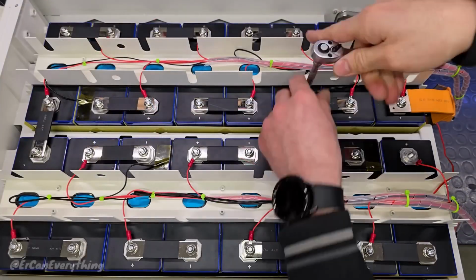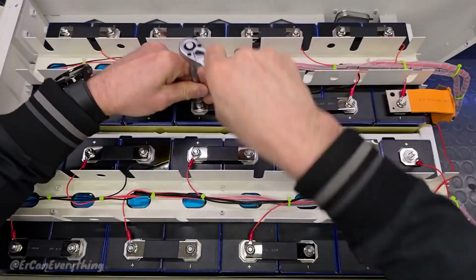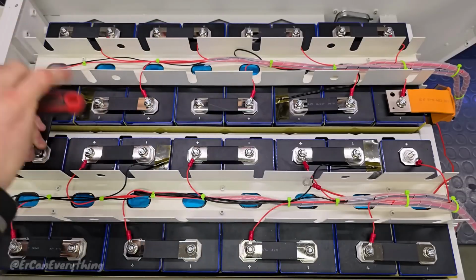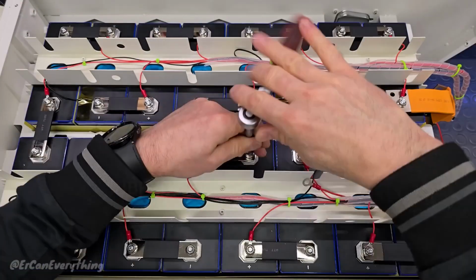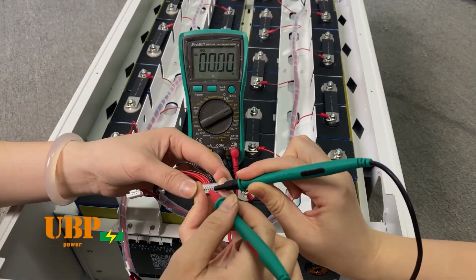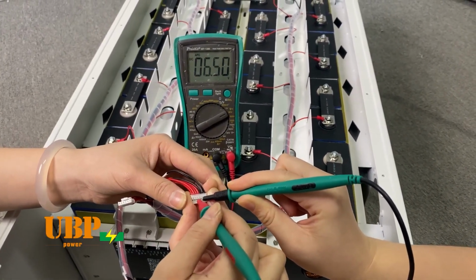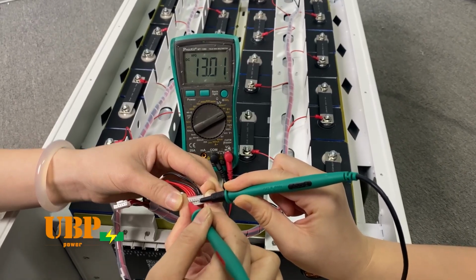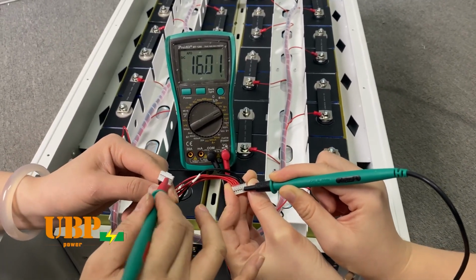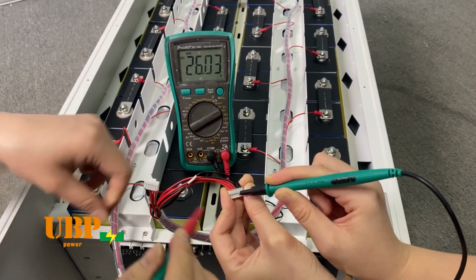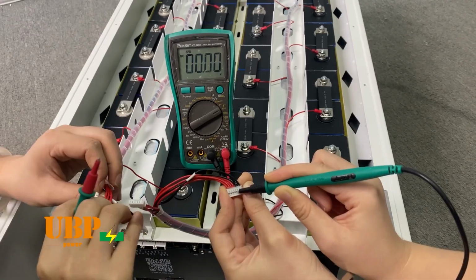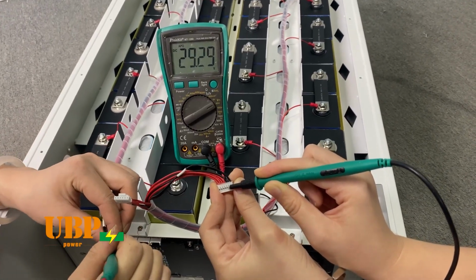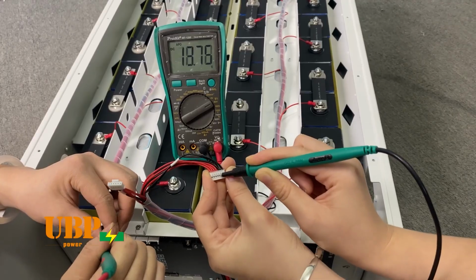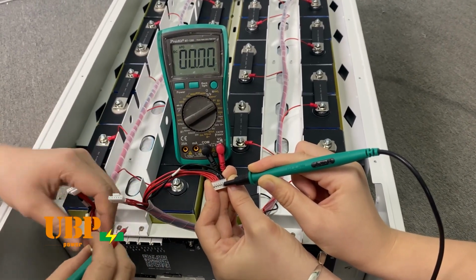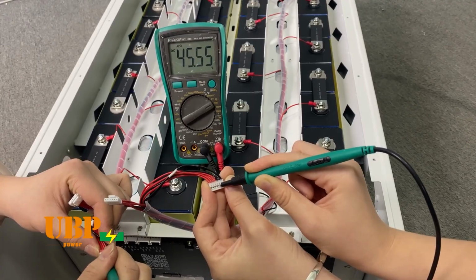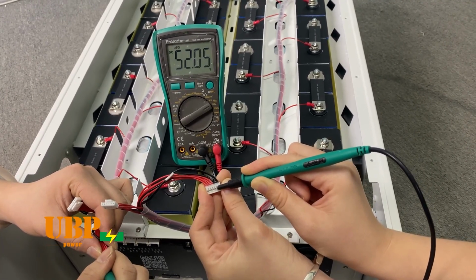Next, tighten each nut on the cell terminals between 4 to 6 Newton meters. Next, using a voltmeter and starting with the cable marked 1, probe the black wire and the first red wire next to the black wire, and you should measure approximately 3.25 volts. Keeping the black wire probed and probing the next red wire, you should get a reading of 6.5 volts. As you probe each successive wire, the voltage reading should increase by approximately 3.25 volts until you reach the final red wire in cable bunch number 4, where you should get a reading of approximately 52 volts DC.